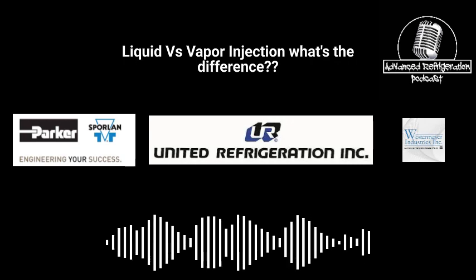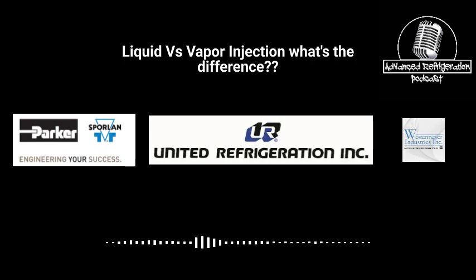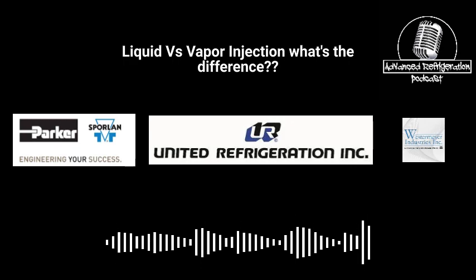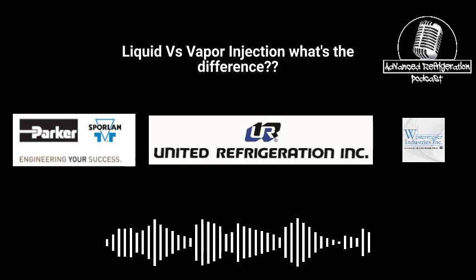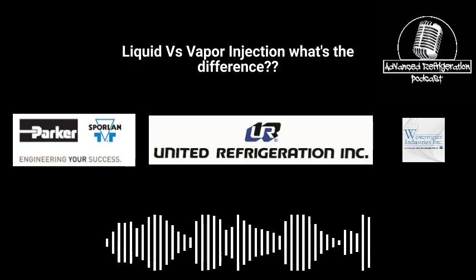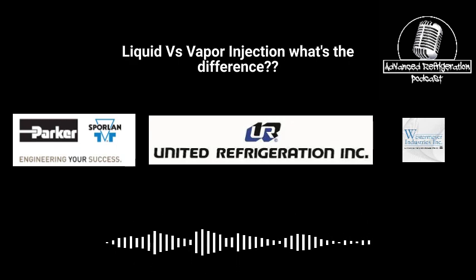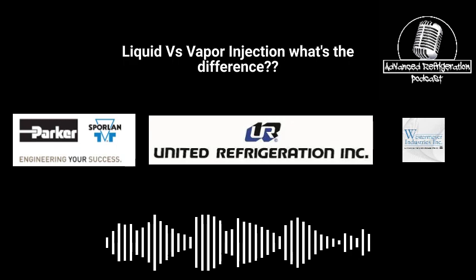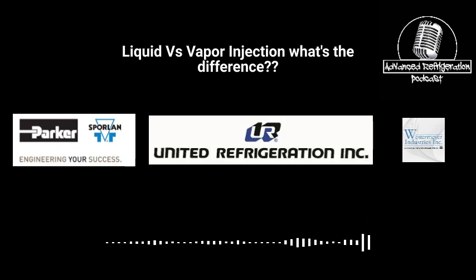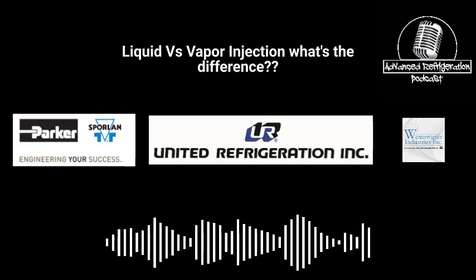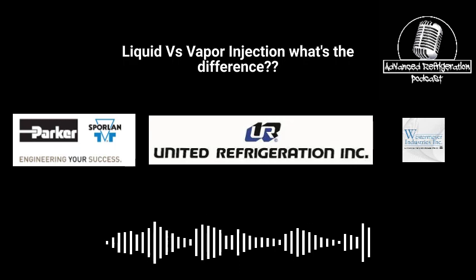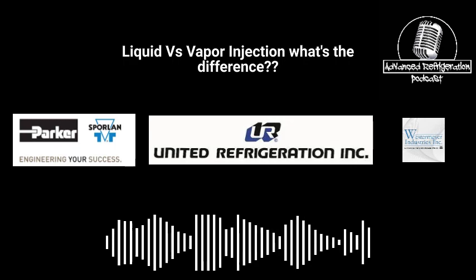Yep. So it's a weird thing with those scroll racks. When they start flooding back that bad and you start loading up the oil separator full of liquid refrigerant, the OMBs don't care if it's liquid refrigerant, water, oil, they don't care. But here's the thing, liquid refrigerant flows way slower through that orifice in the oil feed valve, and it causes it to flash off because it's feeding liquid through there, not oil. Oil doesn't flash off. So it's causing that refrigeration effect inside the crankcase of the compressor, but at the same time, it's also not filling up the compressor fast enough.